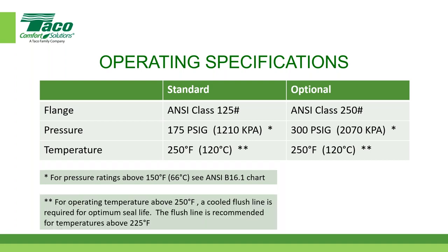And for operating temperatures above 250, you can get it, but a cooled flush line is required for optimum seal life. We actually recommend that you do one for above 225 as well. You can get more information from your rep on that. It's a seal flush line to keep the seal cool.